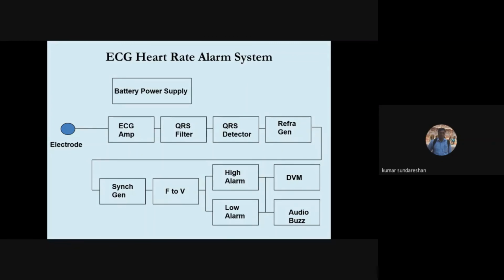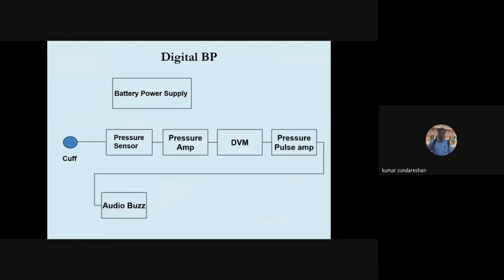So this is how we can look at building medical devices in terms of building blocks. This way it becomes easy for us to interpret and also know what the electronics inside is and where we have to focus. For example, I've taken this example of a BP, blood pressure. You have the pressure sensor in the cuff, you have the pressure amplifier, a DVM, a pressure pulse amplifier, and there are different algorithms that can be used. Normally it is deflating algorithms. Sometimes in some exceptional cases, there are also algorithms for the inflation stage, where when the pressure is inflating, it starts analyzing. In most cases, they use the deflating algorithm.